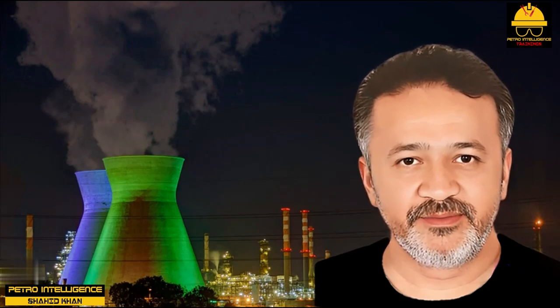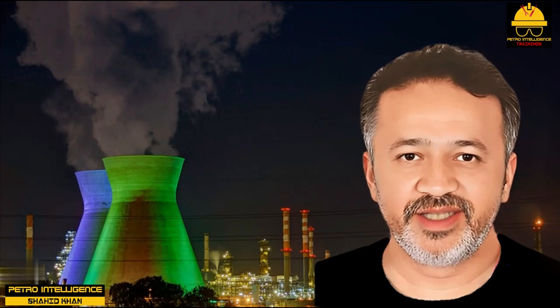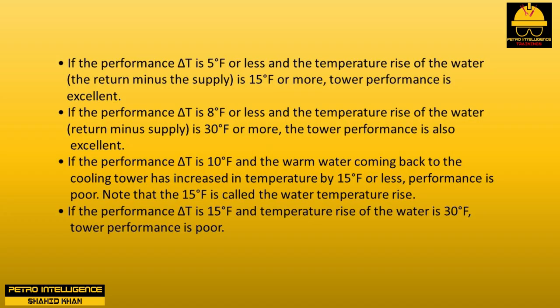Calculate the performance delta T: this is the difference between the water leaving the tower and the wet bulb temperature. Judge the performance of the cooling tower as follows: if the performance delta T is 5°F or less and the temperature rise of the water (return minus supply) is 15°F or more, tower performance is excellent. If the performance delta T is 8°F or less and the temperature rise of the water is 30°F or more, tower performance is also excellent. If the performance delta T is 10°F and the warm water coming back has increased in temperature by 15°F or less, performance is poor.